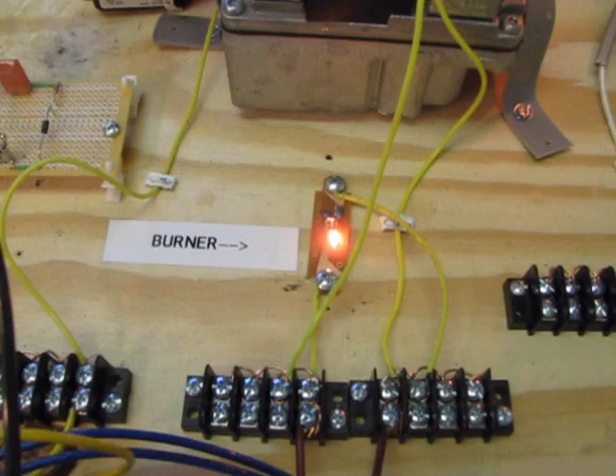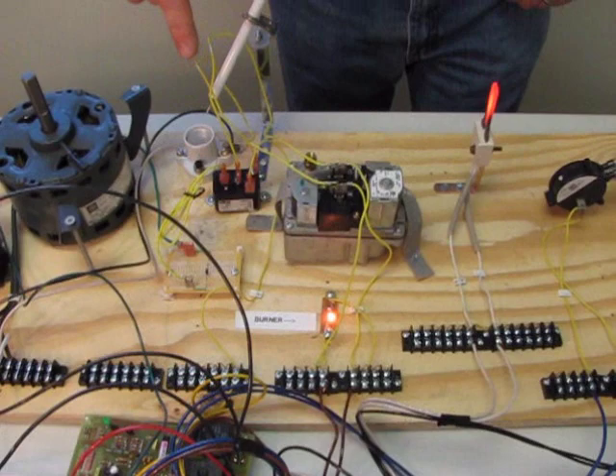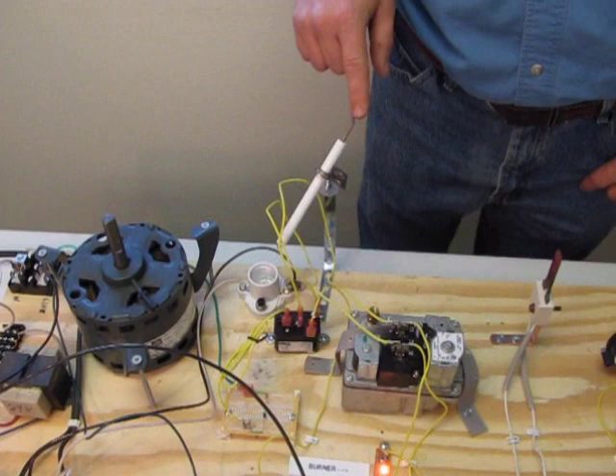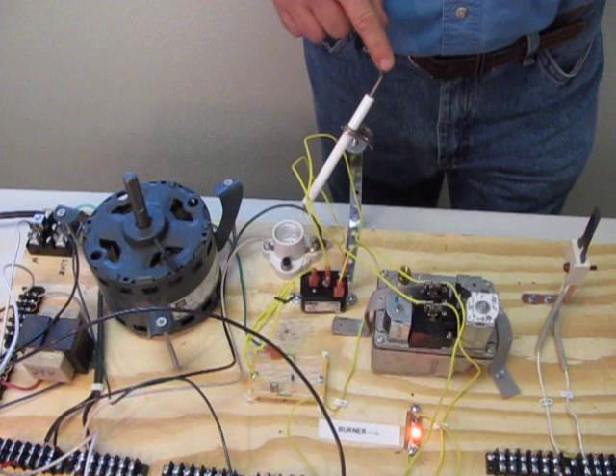The gas valve has clicked, and then that light indicates our burner. That means the burner is running. Now in a typical furnace, when that burner runs, this flame sensor here has got to sense that flame. If it does not sense the flame, it's going to shut down the furnace.